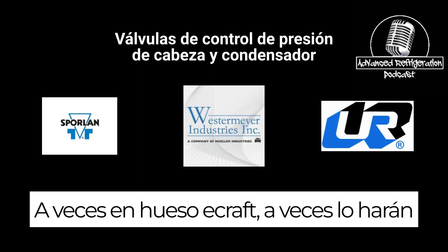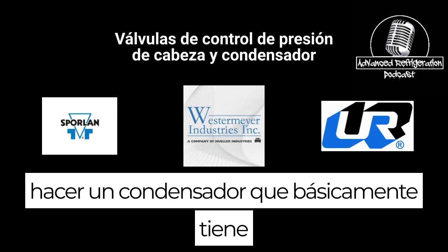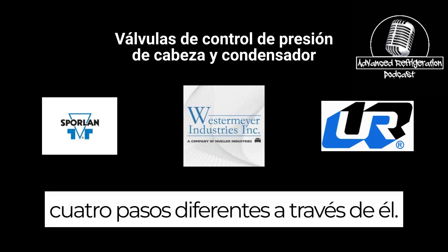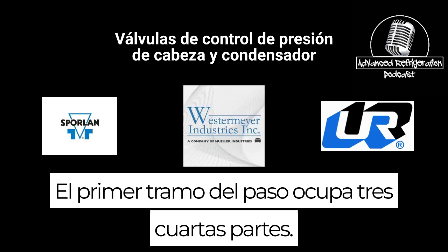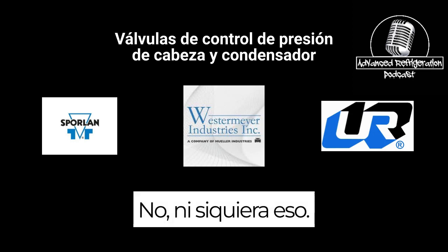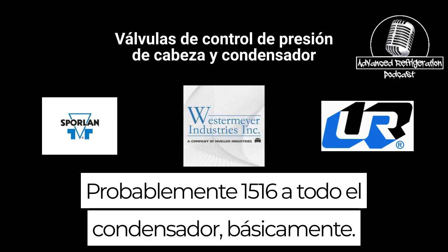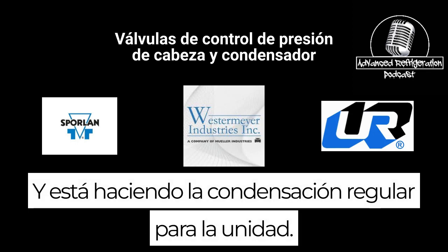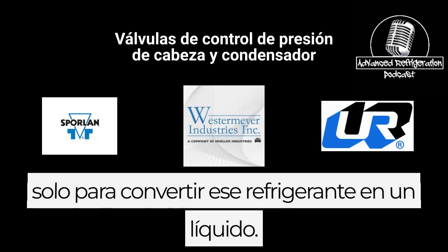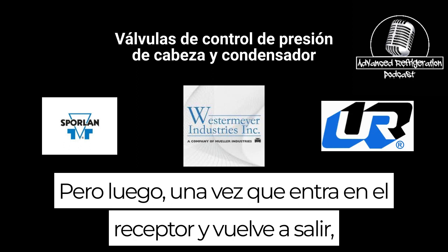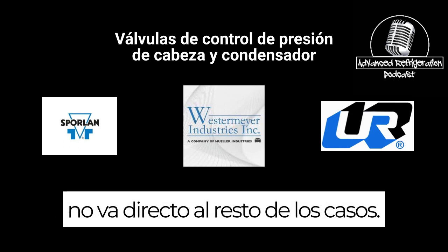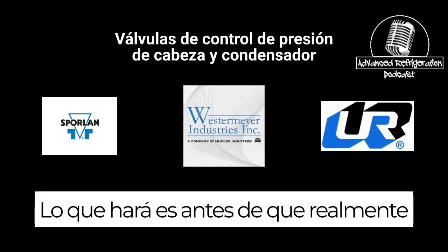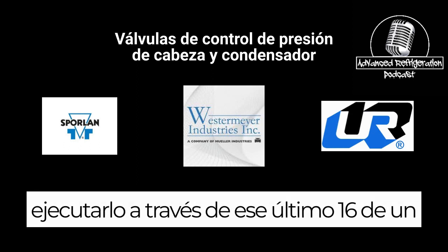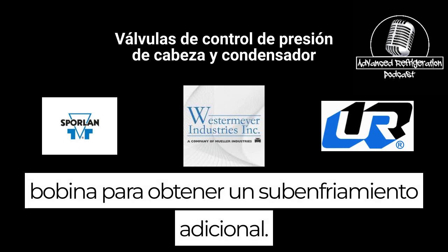Sometimes on certain units, they'll make a condenser that basically has two different passes through it. The first section takes up probably 15/16 of the whole condenser, and it's doing the regular condensing for the unit itself, just to convert that refrigerant into a liquid. But then once it goes into the receiver and back out, it doesn't go straight down to the rest of the cases. What it'll do is, before that, run it through that last 16th of the coil to get some additional subcooling.